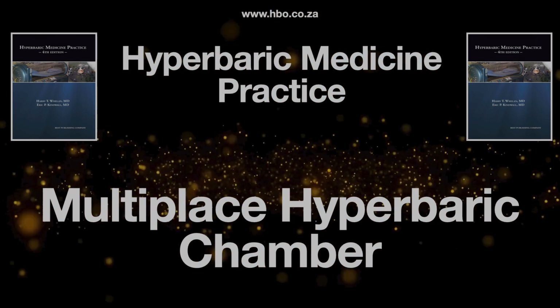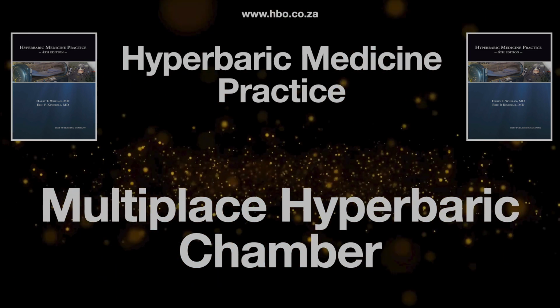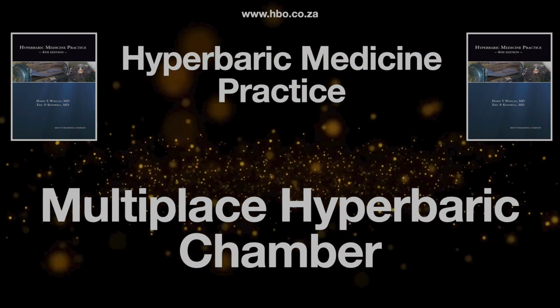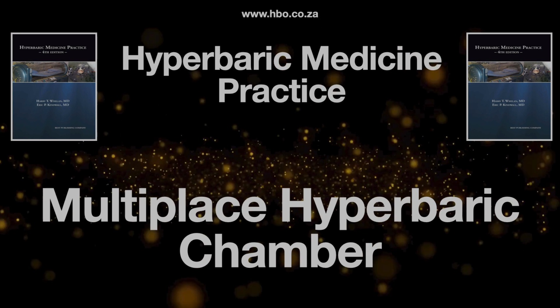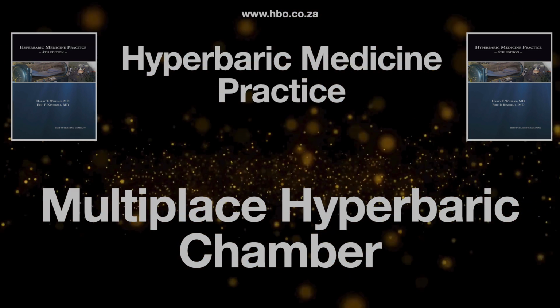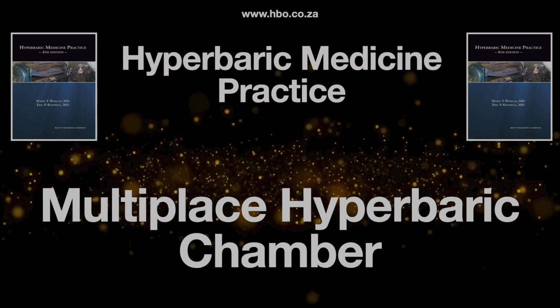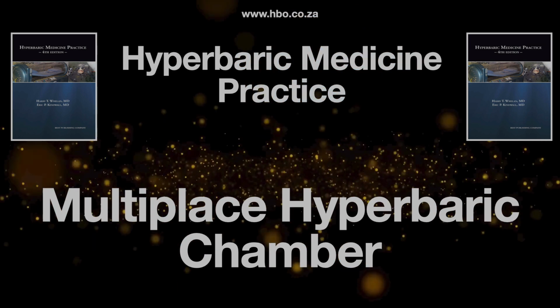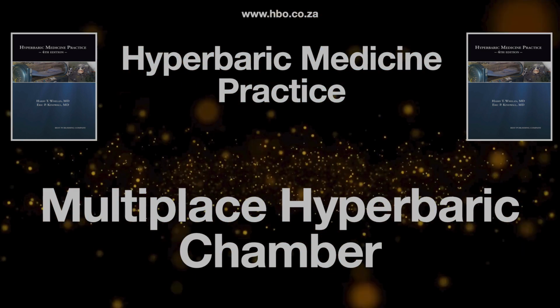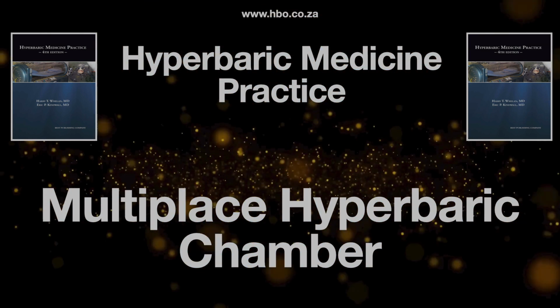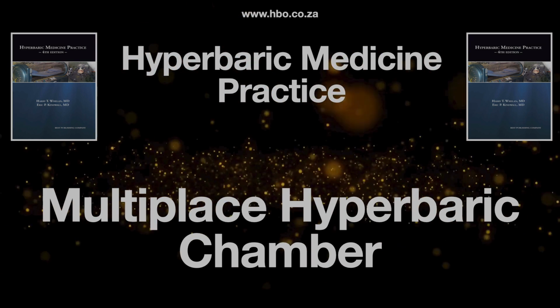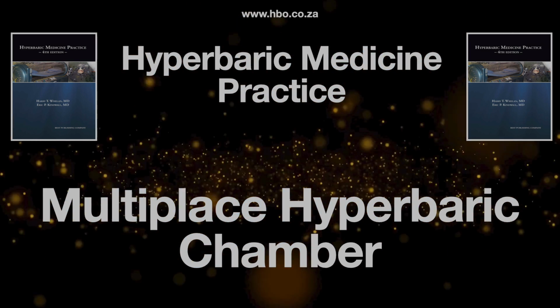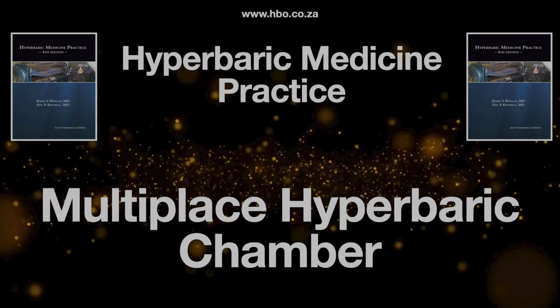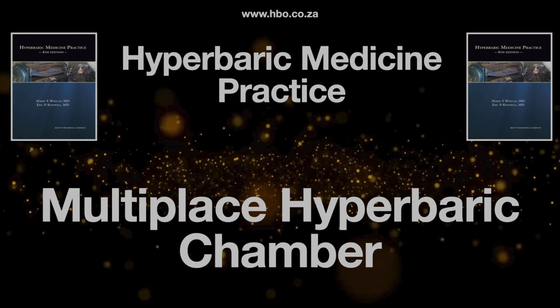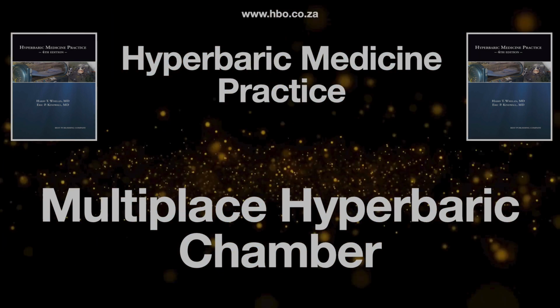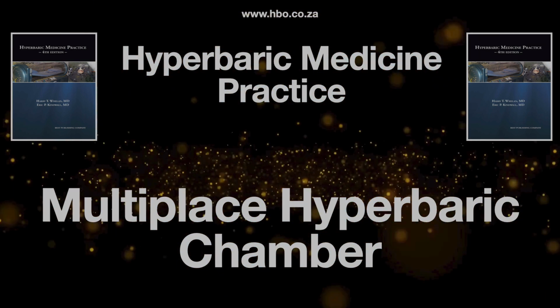That sounds like a lot of water. It is. It could be around 1,000 liters per minute total for a typical chamber. Massive amount delivered almost instantly. How is it triggered? Usually there are dual opposing fire extinguishing systems. Yeah. CE identified, so they meet those EU standards. Activation needs 2 separate sensors to detect flames simultaneously within like 1 second. Helps prevent false alarms. Okay, very fast, very specific trigger. Right. But there's also a manual override. You can deactivate it within maybe 3 seconds if something non-fire related triggers the sensors.